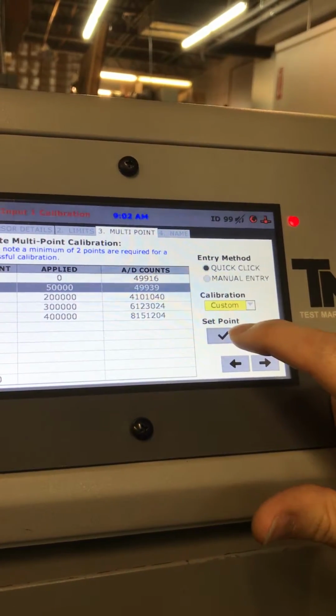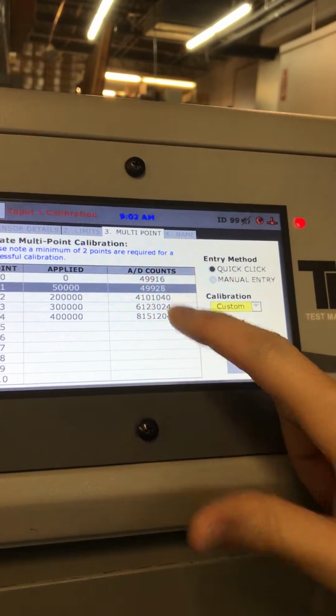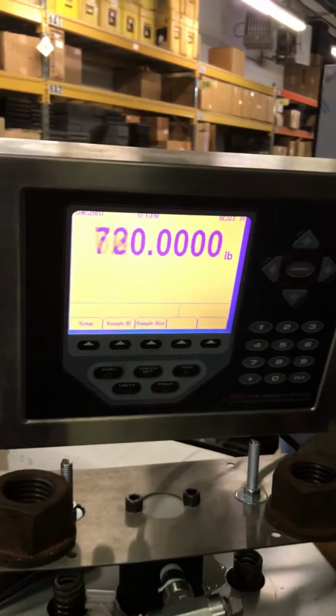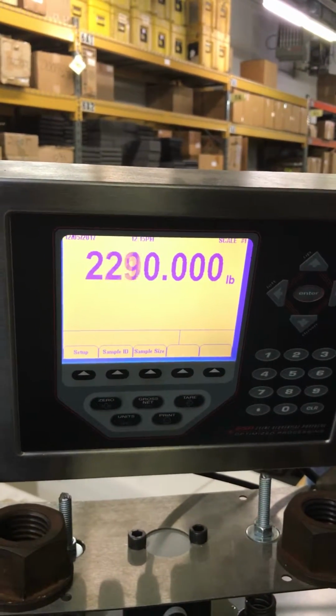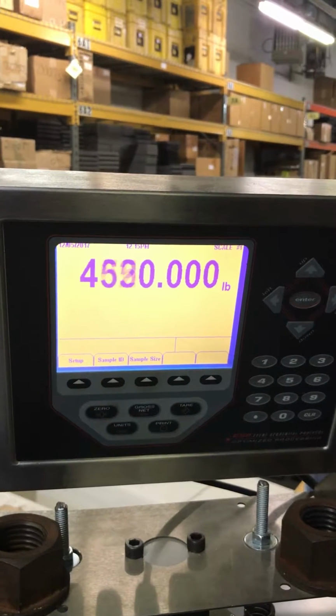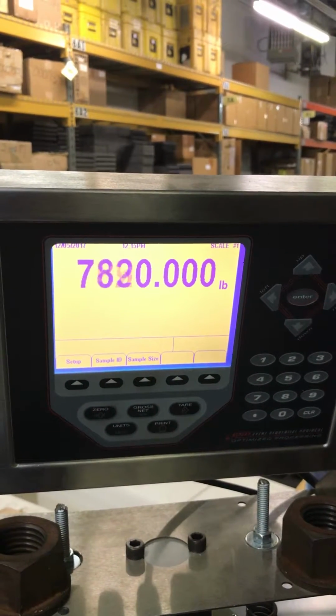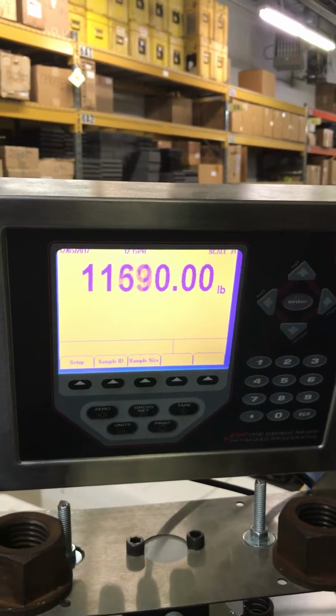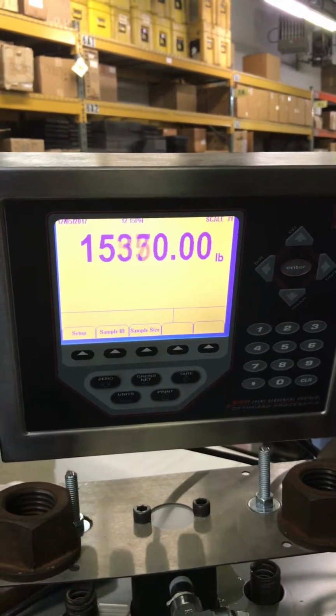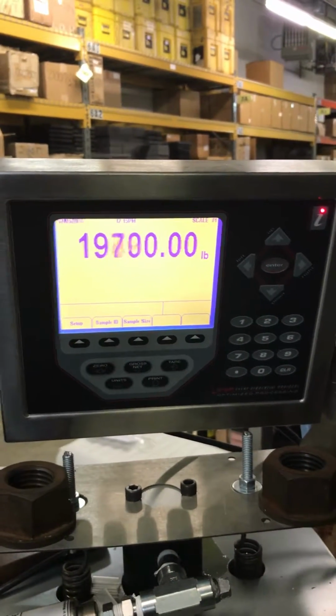So we'll clear that point. And it's showing the A to D counts there. So we'll run our calibration instrument up to 50,000. And we didn't start at 0, so this isn't really an accurate calibration, but just for example purposes. Yeah, this is just to show the process.